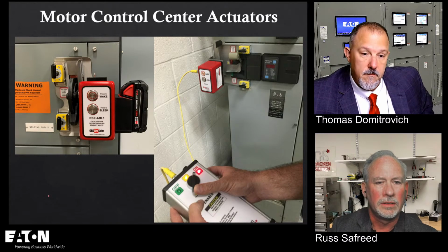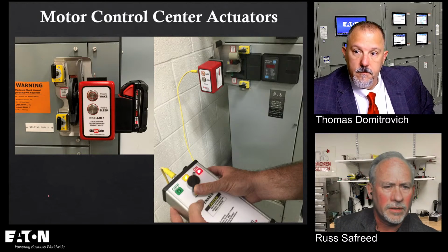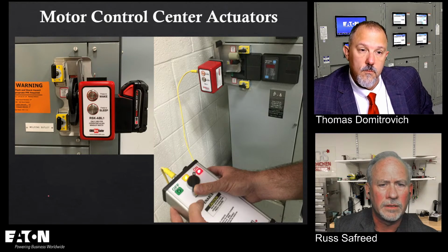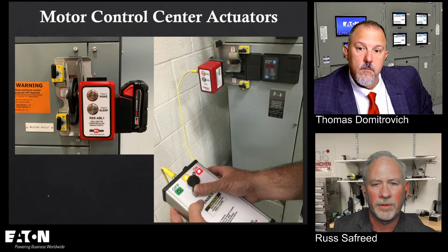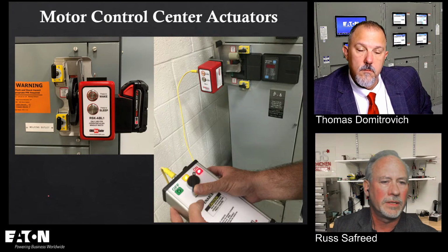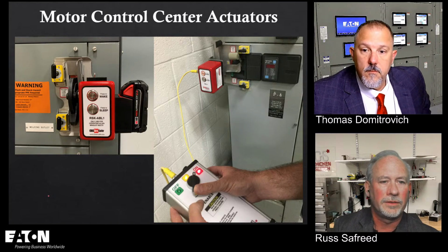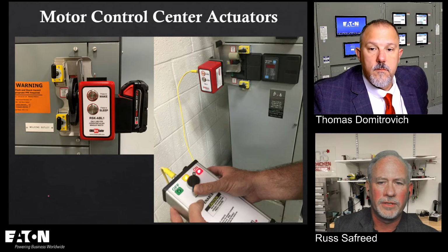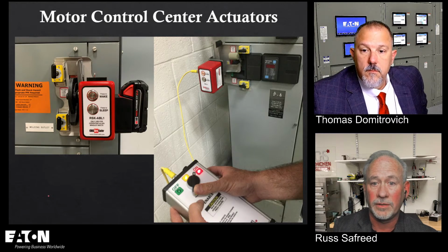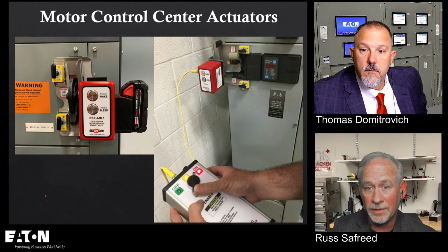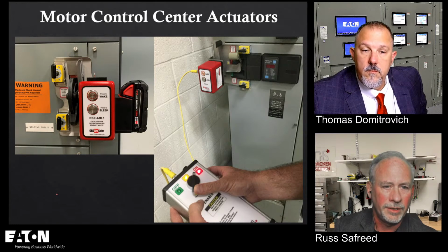They'll easily work in our building here 100 feet apart. These pictures show devices that go on motor control centers, to actuate them. We have lots to pick from. One thing we tried to point out when coming out with these, going back to the risk severity idea, motor control centers usually don't have as much arc flash energy typically as substation breakers. They can, but as a whole, they probably don't.